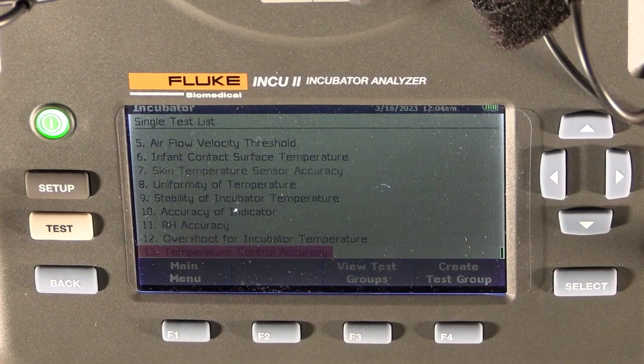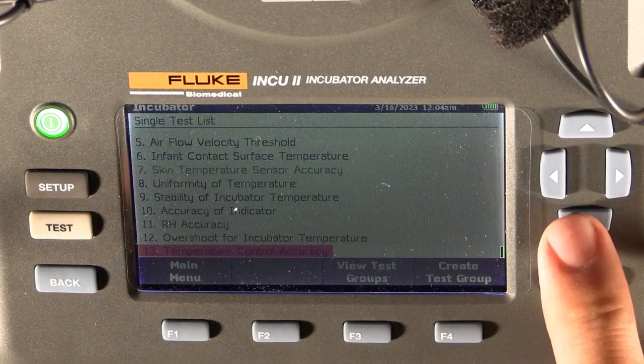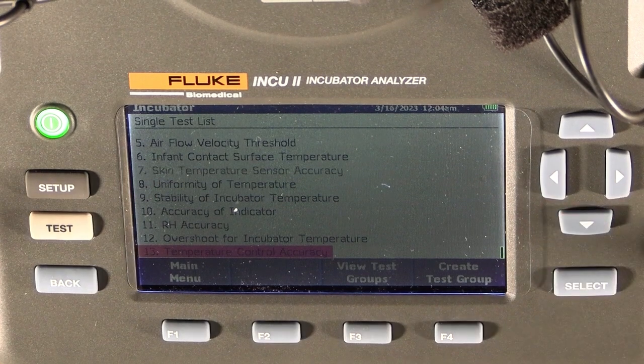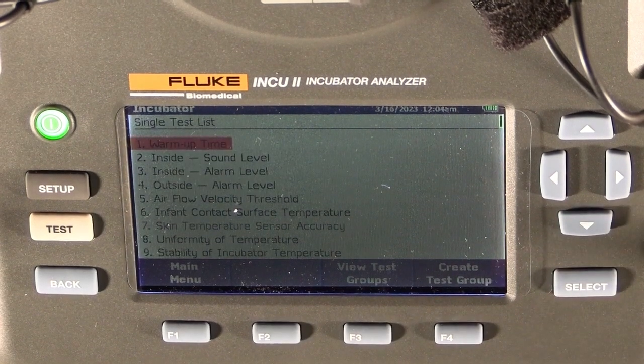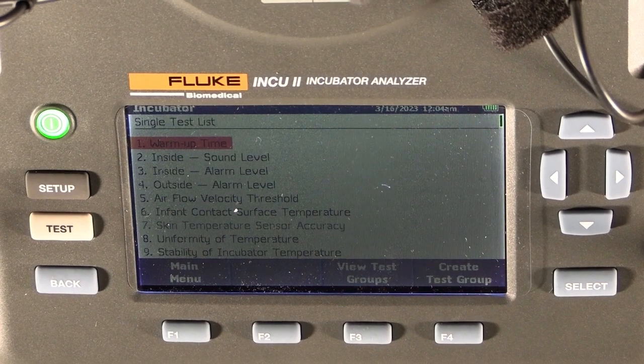Temperature control accuracy. Again, we wait for the stability of the unit and we compare our measured result from inside the incubator to the set temperature of the incubator. Just note the difference between the temperature control accuracy and the accuracy of the indicator. Accuracy of the indicator is the measured value from the incubator compared to our inside temperature, and the control temperature is the measured value compared to the set temperature on the controls. So just remember the difference between the two of them. And yeah, that is the list for the incubator.